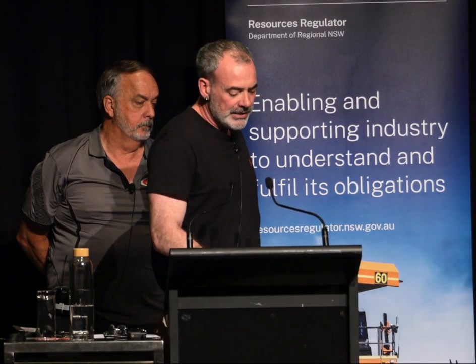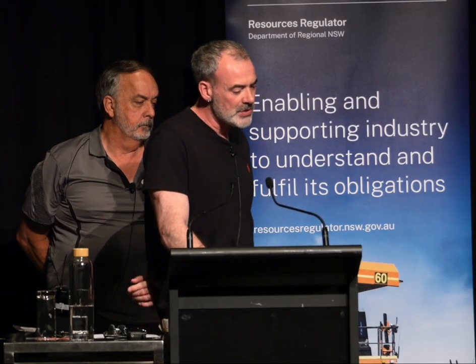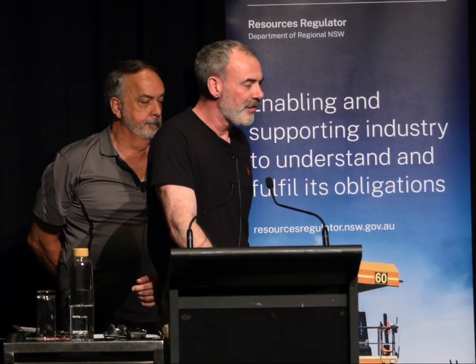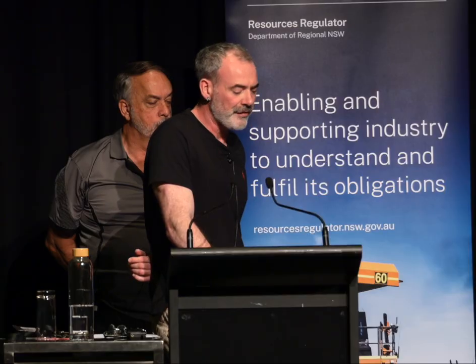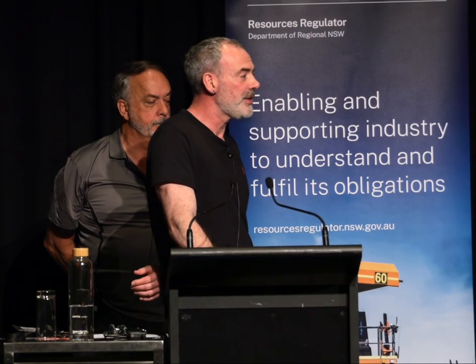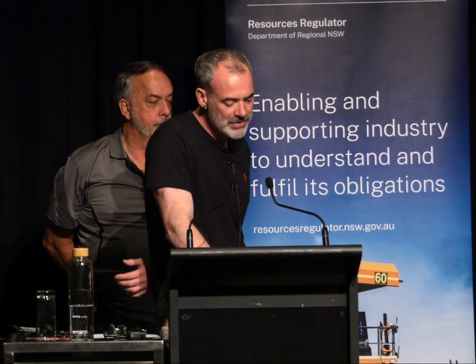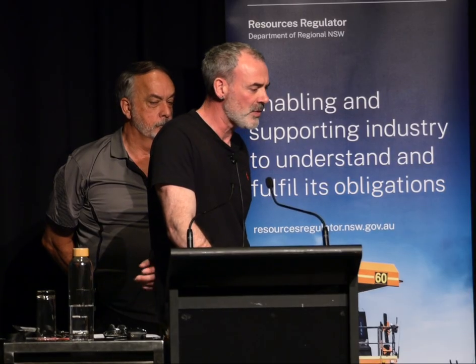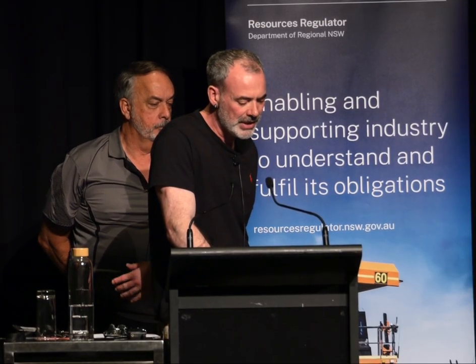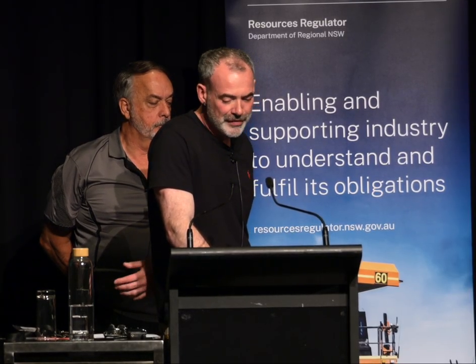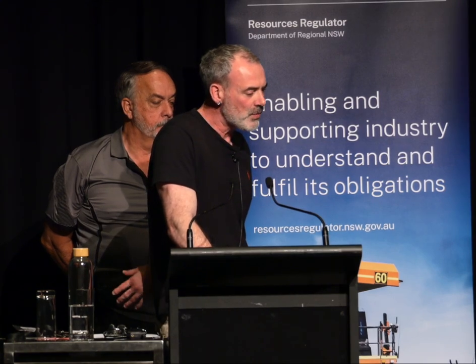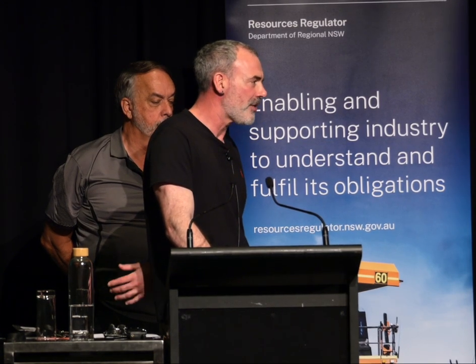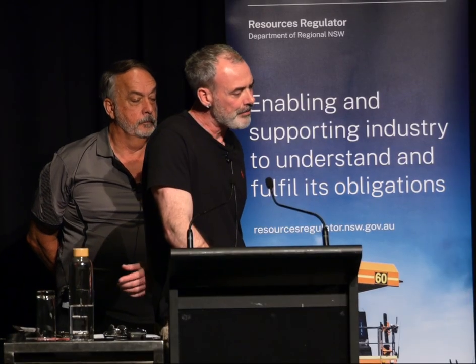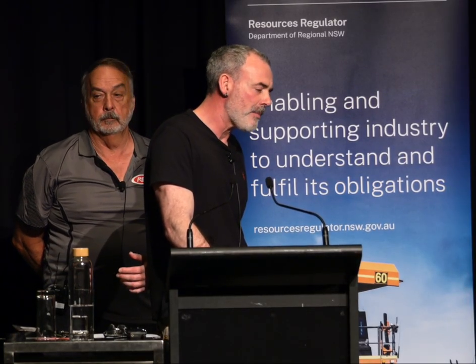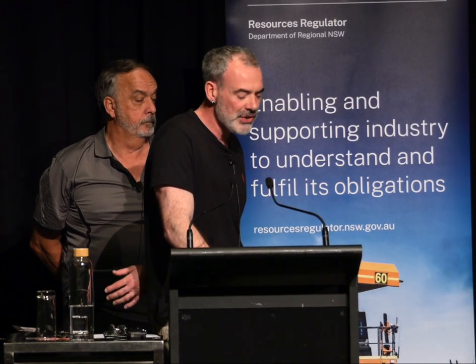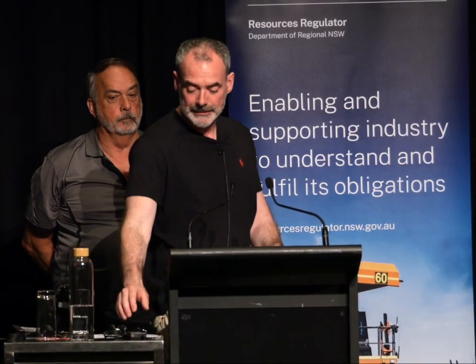So about the age and the condition of the transformer, we'll do a visual inspection of the asset, review the dissolved gas analysis results, the furan analysis results to assess the condition of the paper, look at the electrical testing results. So a transformer, for instance, with heavily degraded paper insulation might not be a good candidate for a retrofill. There might be some complications with certain types of bushings. Look at the electrical test results. Confirm with the OEM of your on-load tap changer if you wish to do a retrofill of that.